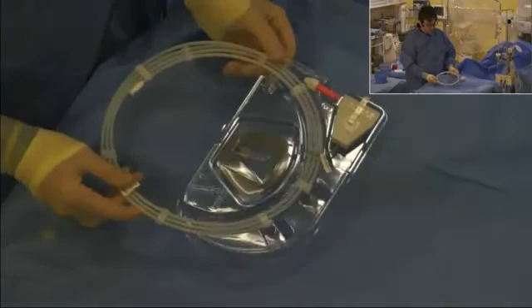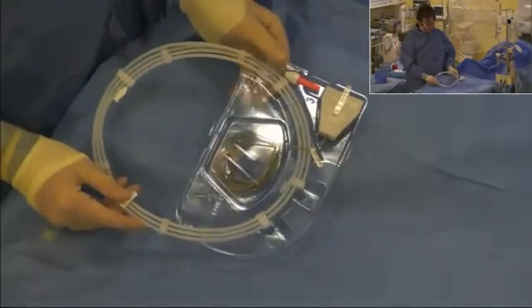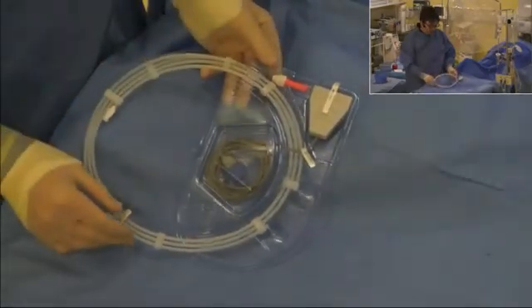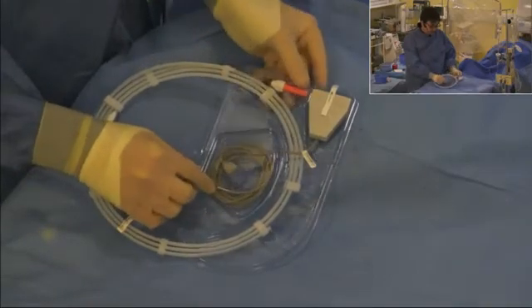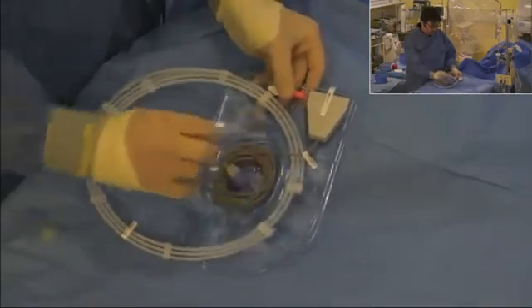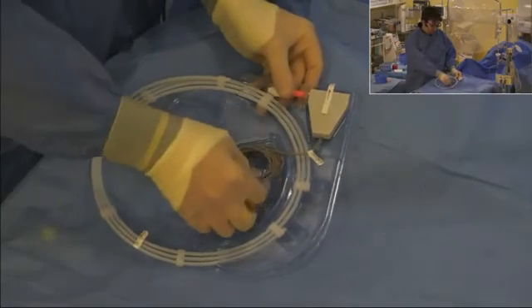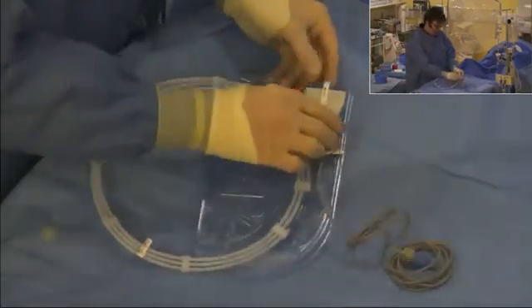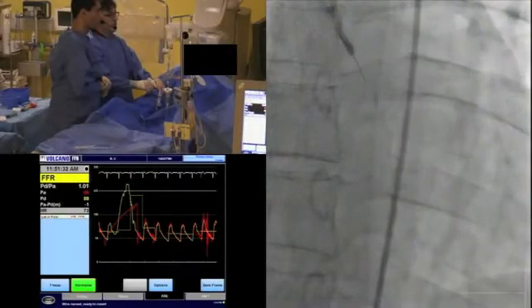Great, so this is the new Verrata pressure wire. You can see the pressure wire as it comes in the pack here. It's all nicely assembled. The first thing I'm going to do is release the door here. You've got the little cable, and you see the actual wire itself is fixed in. I'm just normalizing in this position, which is what I'm going to do.